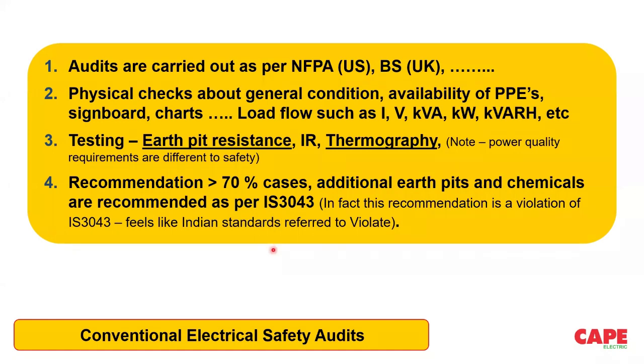As a member of ETD 20, I know very well that this chemical earth or this additional earth pit is not going to help you. If anybody wants to recommend chemical earth pits, you recommend, we have no issue. But the problem is, don't claim that it is as per IS 3043, because IS 3043 is never written in this fashion. In fact, this chemical earth or these additional earth pits is actually a violation of the standard. So by looking at the safety audit reports, what we feel is Indian standards are referred only to violate, whereas all the other standards like NFPA, BS are mentioned in the reports. The client most of the time doesn't know what the NFPA says or the BS standard says. Actually, these high-sounding names like NFPA, BS and all are big names so that people are convinced easily. That is actually not necessary.